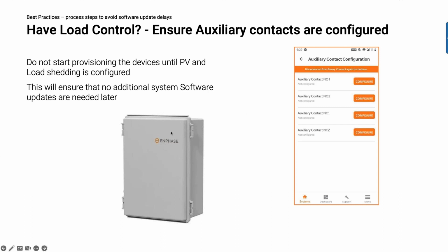You can have up to 4 of these contacts if you've got 2 load control boxes. You want to make sure that you configure these before you commission the entire system. Sometimes people don't know that they need to configure this, they just bypass it. You commission the system, and then you think, oh, these aren't working the way they should. If you configure it afterwards, it'll perhaps go through a second software update to configure this properly. So the best thing to do is to configure this before you commission the system, and then you're going to be taking the smoothest path forward.